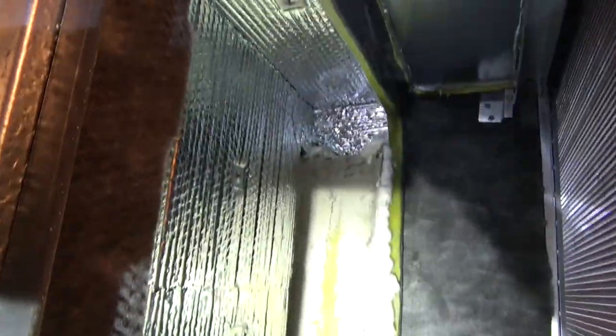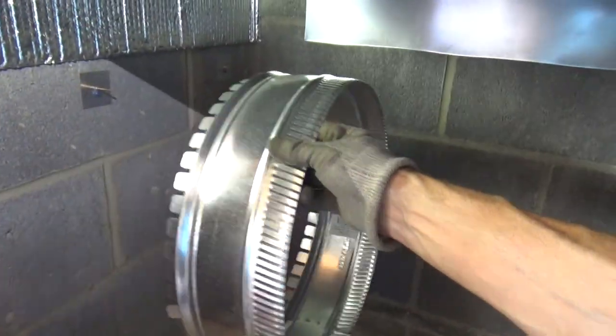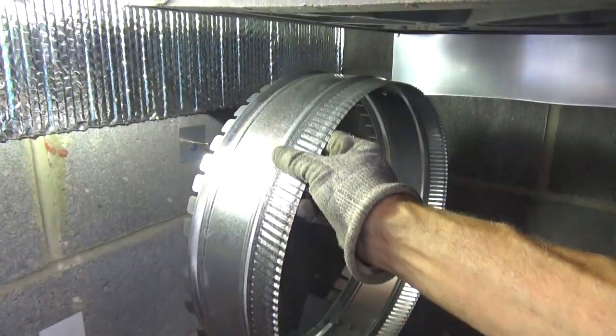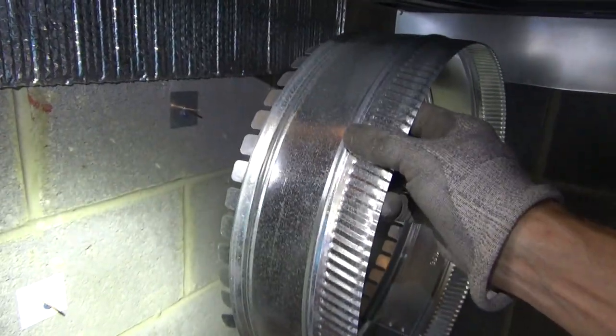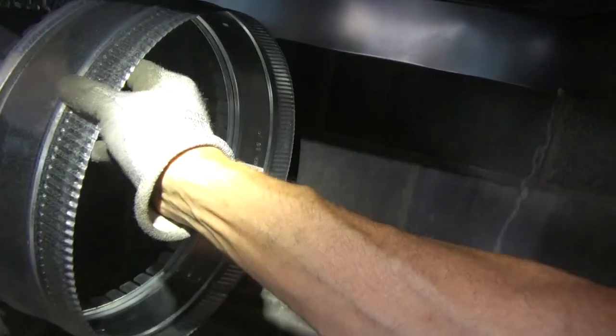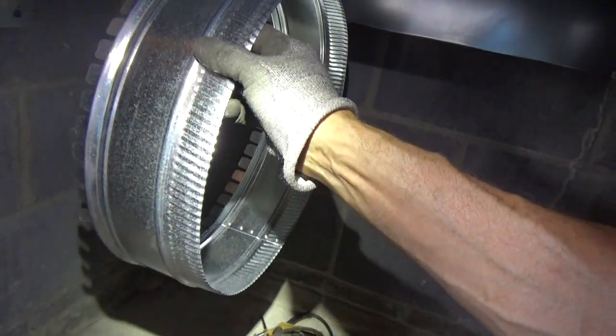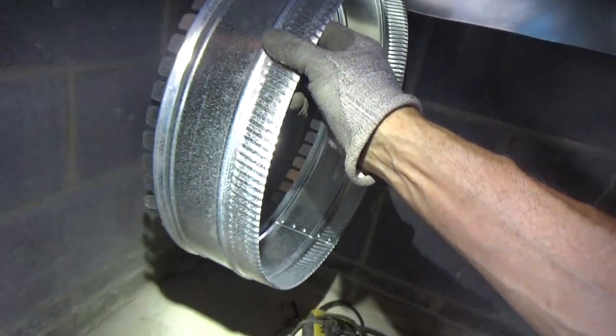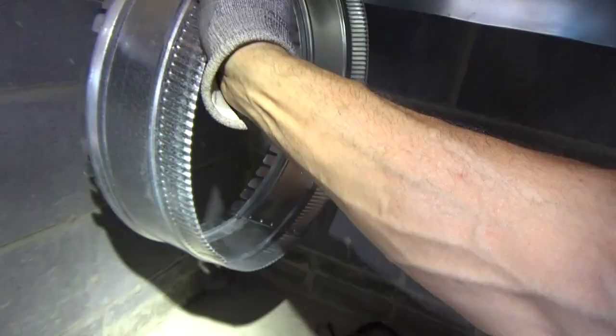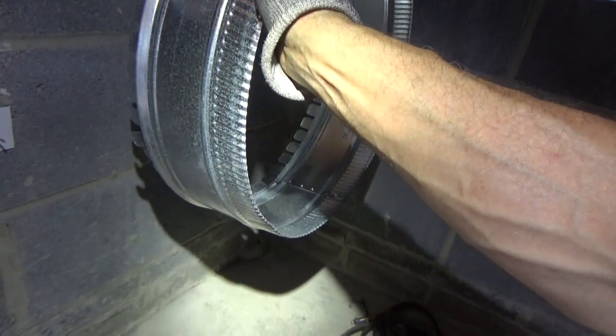So I'm sealed at the top, sealed on the sides, sealed on that side, top back there. Now I need to make the return, and I don't want to just put this on the 5.5 inch. I want to bring it back a little bit, because with airflow, if it looks like it has good airflow, it will. And if it looks like it's a bottleneck, it's bad airflow.